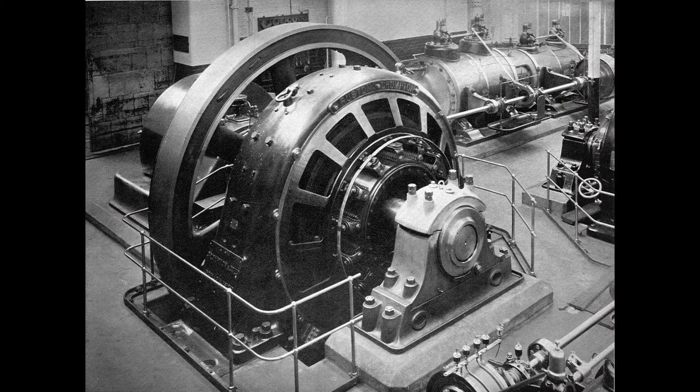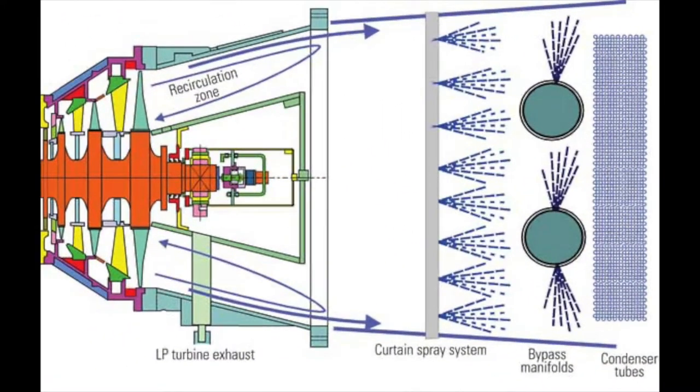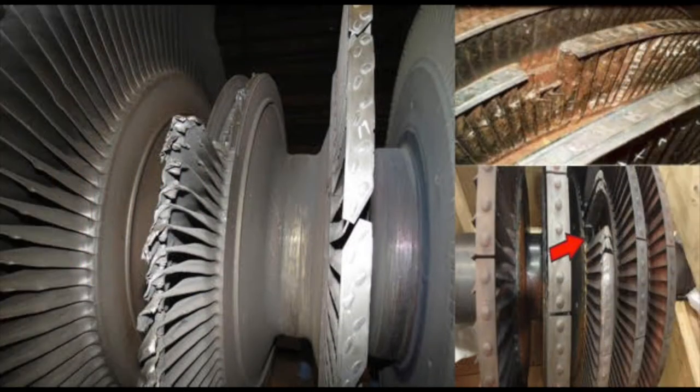Operating at the low extreme of the steam turbine's capacity is causing undesirable flow conditions, particularly near the last set of turbine blades. It's been observed that ramping down capacity causes steam flow to reverse and travel back into the turbine blades, which causes vibrations and can lead to costly fractures and wear and tear.